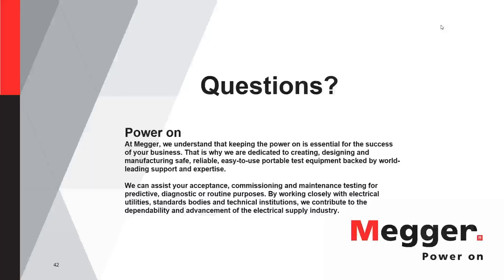Okay, and one more for you, Jason. Overall, which methods could be used when the system is on, and which ones need shut down to do testing? So all of the methods that Robert talked about today are for when the cable's out of service, de-energized, and made safe before you touch it, before you work on it. None of the methods today work with a cable that's in service.